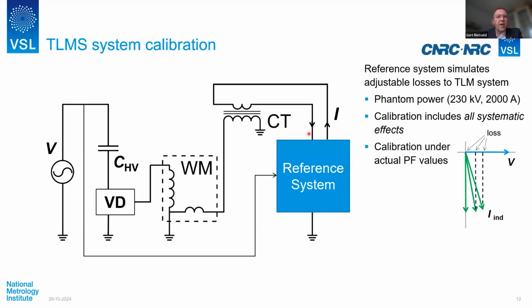So both the NRC Canada and VSL Netherlands systems use this approach of simulating a power transformer with certain losses to the measurement system of the industry. So at power factor 1, I already mentioned 3% is to be achieved. The specification by the instrumentation manufacturers, the manufacturers of the voltage divider, current transformer, this part here, the TLMS, is typically 0.5 to 1%.